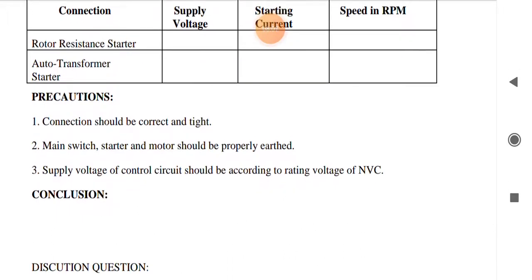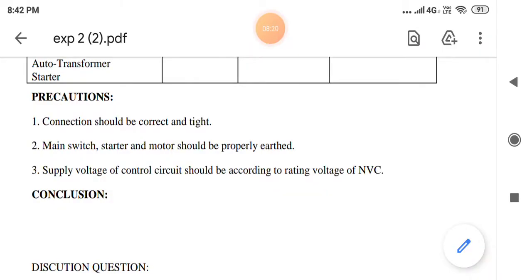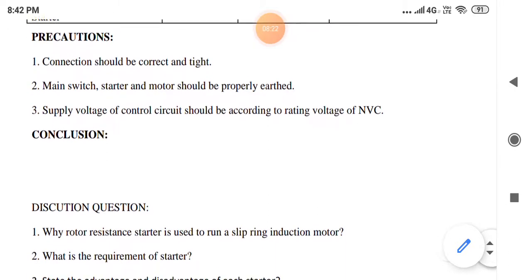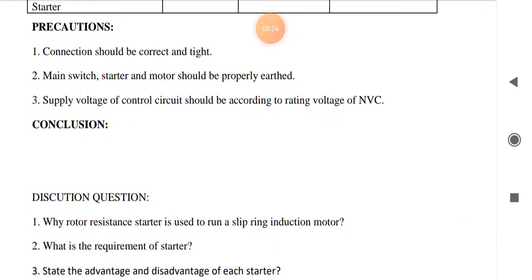Now precautions. The connections should be correct and tight. Main switch, starter and motor should be properly earthed. The supply voltage of the control circuit should be according to the rating voltage of the NVC.